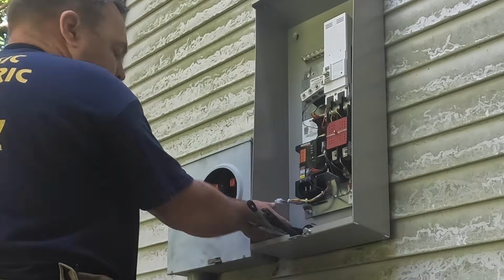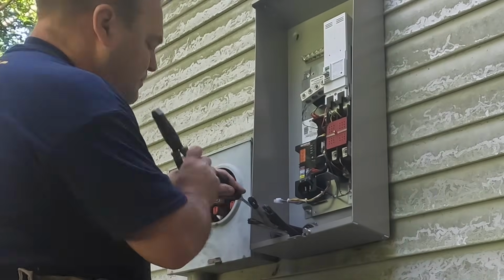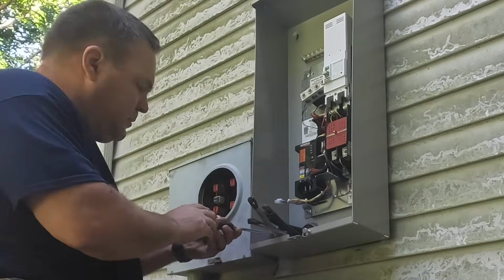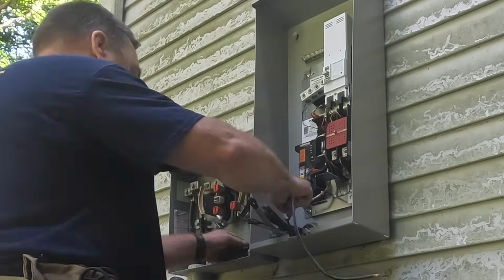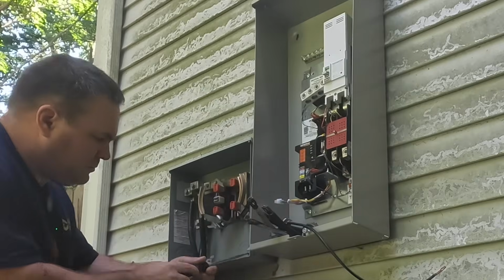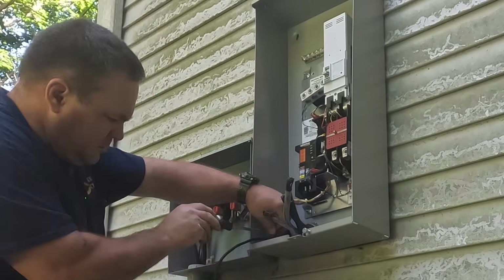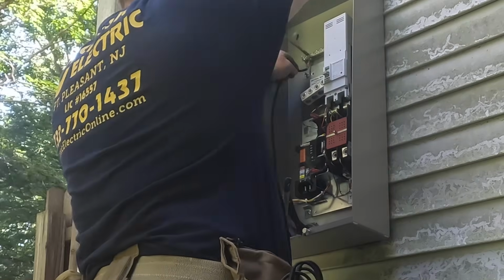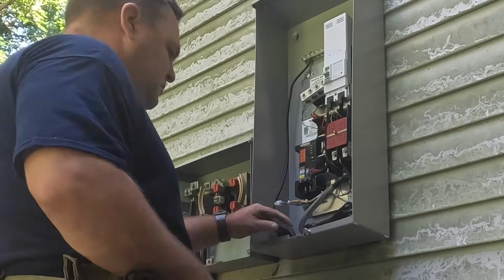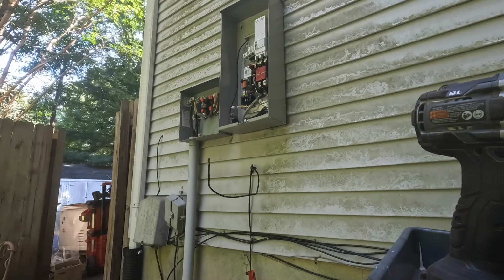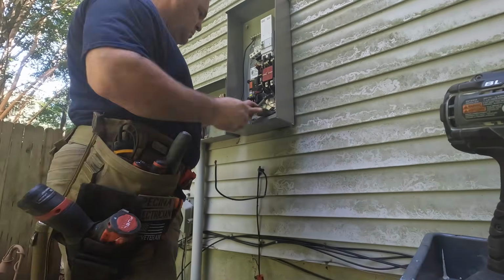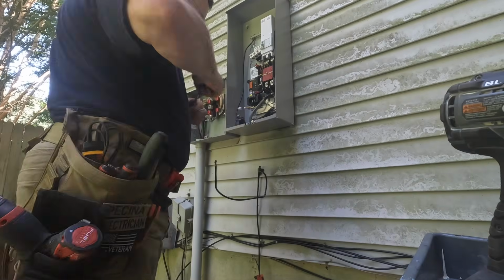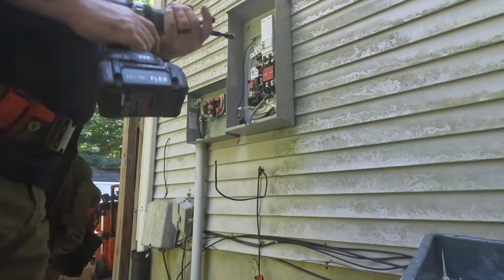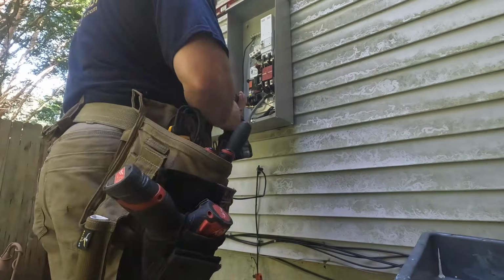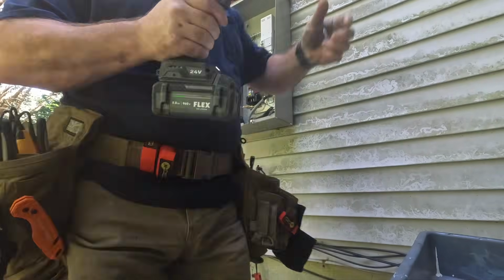The automatic transfer switch is rated at 200 amps, and it's a service-rated disconnect switch, which means the National Electric Code can recognize this piece of equipment as service-rated. So you can use it here as I am. This is going to be the main disconnect of the house, so when utility power is lost, it's going to send a message to the generator to start up, and approximately 10 seconds later, the generator will have started and transfer the load automatically.